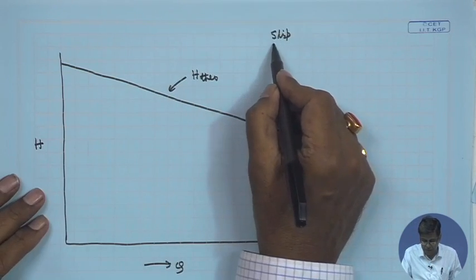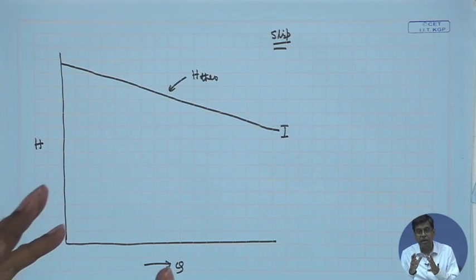first we take slip, as we defined slip as the phenomena that happens because of the pressure difference at the leading and the trailing sides of the blades, for which there is a circulation and non-uniformity of velocity in the blade passage, which reduces the tangential component of flow velocity at the outlet and reduces thus the head developed or the energy imparted to the fluid by the pump, and this slip phenomena is independent of viscosity, and it is purely the influence of curvature of the blade, and this is 0 when the flow is 0, and at low flow this is low.